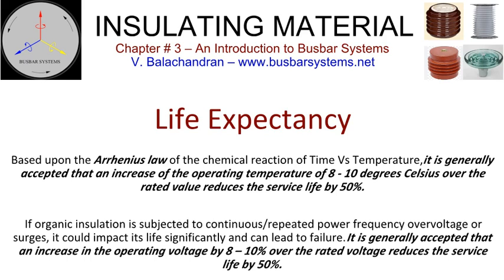Similarly, an insulation system is designed for an operating voltage. If organic insulation is subjected to continuous, repeated power frequency overvoltage or surges, it could impact its life significantly and can lead to failure. It is generally accepted that an increase in the operating voltage by 8 to 10% over the rated voltage reduces the service life by 50%.